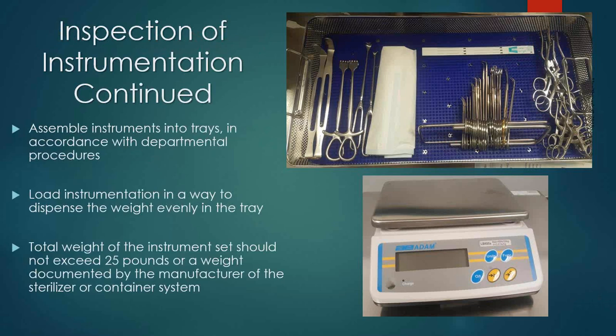So you want to make sure that you assemble instruments in trays in accordance with department procedures. There could be some standardization that tells you that you must set this from left to right, place from top to bottom - so make sure you're doing that per procedure. Load instrumentation in a way to distribute the weight evenly in the tray for sterilization, as well as to prevent any type of injuries. Total weight of the instrument set should not exceed 25 pounds, or a weight documented by the manufacturer of the sterilizer or container system.